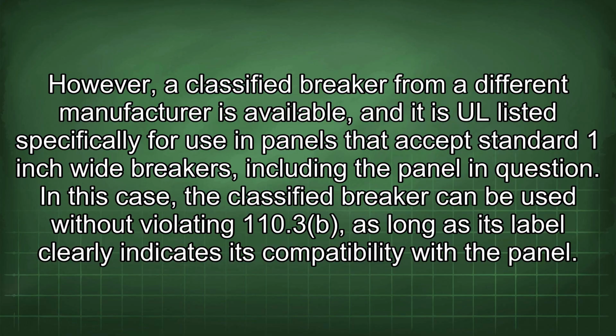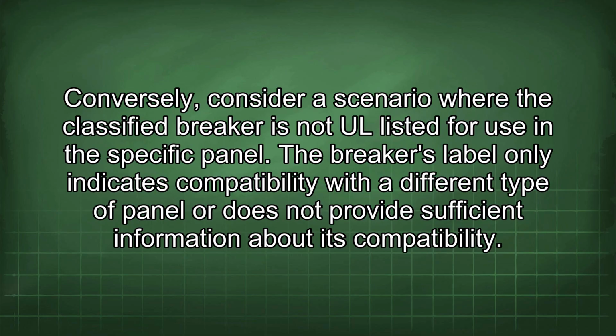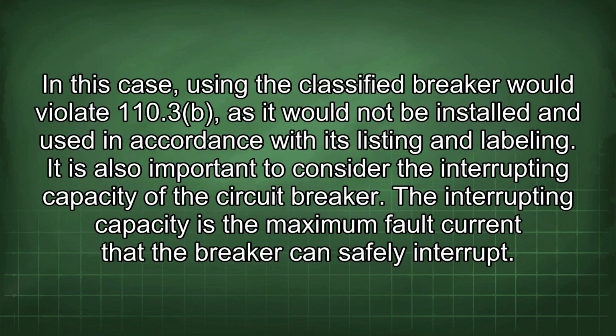compatibility with the panel. Conversely, consider a scenario where the classified breaker is not UL listed for use in the specific panel. The breaker's label only indicates compatibility with a different type of panel or does not provide sufficient information about its compatibility. In this case, using the classified breaker would violate 110.3 as it would not be installed and used in accordance with its listing and labeling.